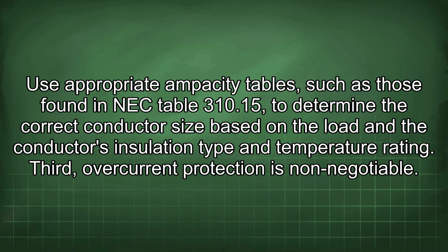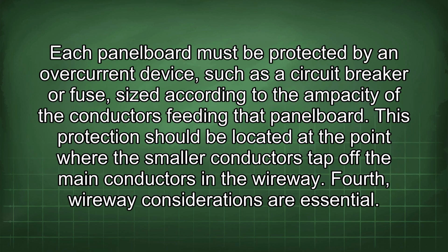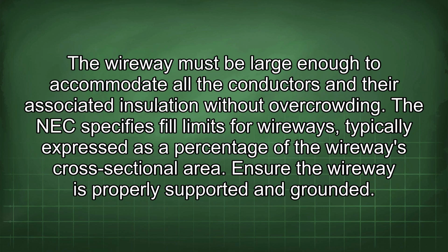Third, overcurrent protection is non-negotiable. Each panel board must be protected by an overcurrent device, such as a circuit breaker or fuse, sized according to the ampacity of the conductors feeding that panel board. This protection should be located at the point where the smaller conductors tap off the main conductors in the wireway. Fourth, wireway considerations are essential. The wireway must be large enough to accommodate all the conductors and their associated insulation without overcrowding. The NEC specifies fill limits for wireways, typically expressed as a percentage of the wireway's cross-sectional area. Ensure the wireway is properly supported and grounded.